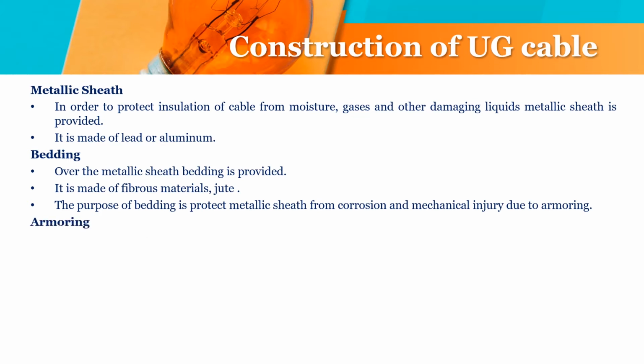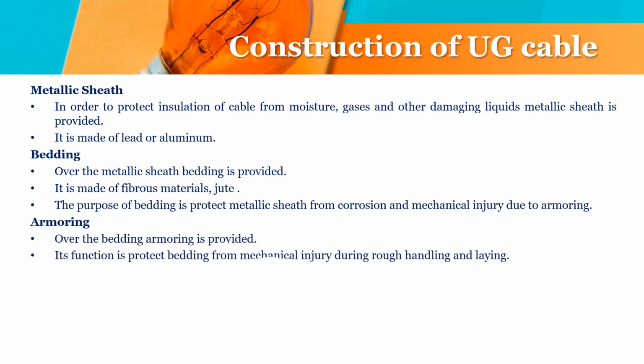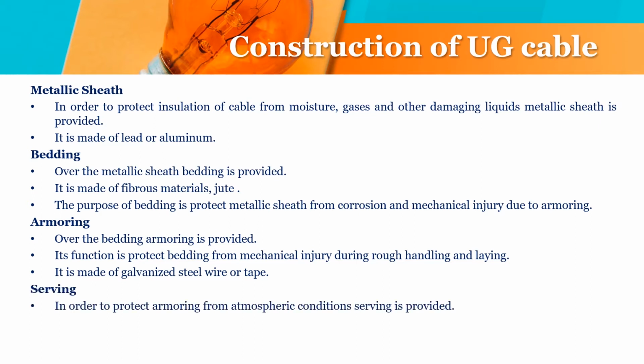Armoring: over the bedding, armoring is provided. Its function is to protect the bedding from mechanical injury during rough handling and laying. It is made of galvanized steel wire or tape. Serving: in order to protect the armoring from atmospheric conditions, serving is provided. It is made of rubber or tape.